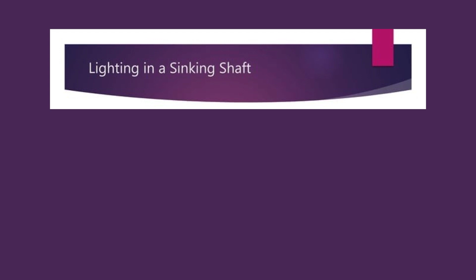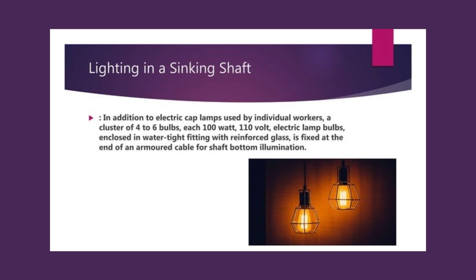In addition to electric cap lamps used by individual workers, a cluster of 4 to 6 bulbs, each 100 watts and 110 volts, enclosed in watertight fittings with reinforced glass, is fixed at the end of an armored cable for shaft bottom illumination.